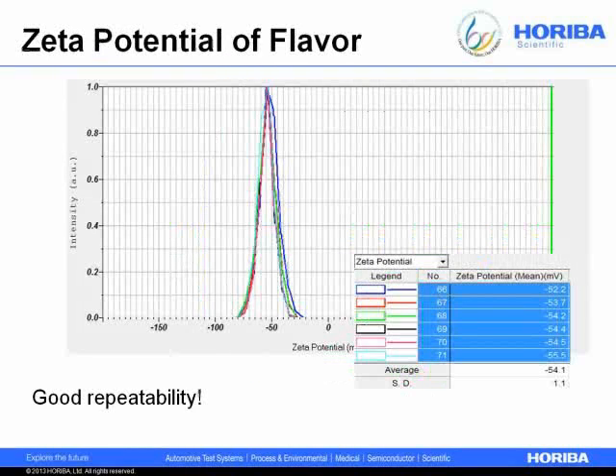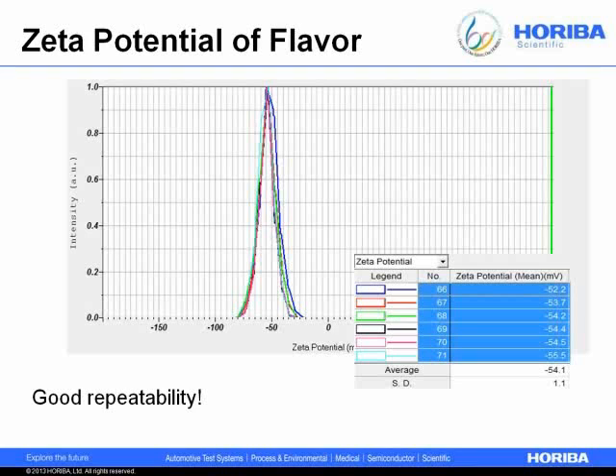The software makes it easy to find the average and standard deviation of a group of measurements. Six repeats of a flavor emulsion give an average zeta potential of minus 54 millivolts with a standard deviation of 1 millivolt, indicating very likely stable suspension. That prediction proved correct — the suspension sat on the desk for quite a while and did not separate.